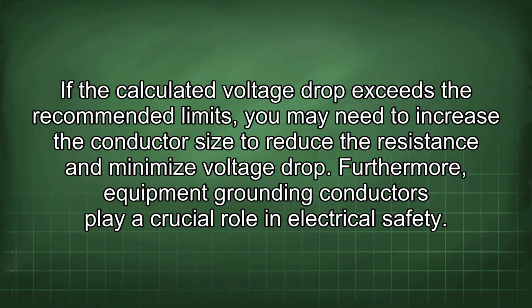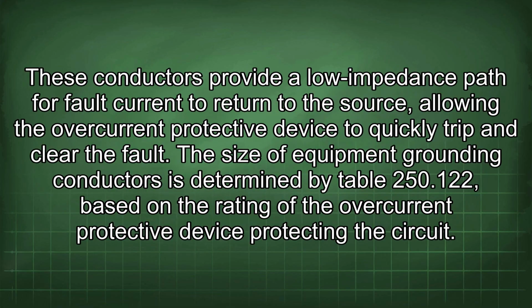Furthermore, equipment grounding conductors play a crucial role in electrical safety. These conductors provide a low impedance path for fault current to return to the source, allowing the overcurrent protective device to quickly trip and clear the fault. The size of equipment grounding conductors is determined by Table 250.122, based on the rating of the overcurrent protective device protecting the circuit.